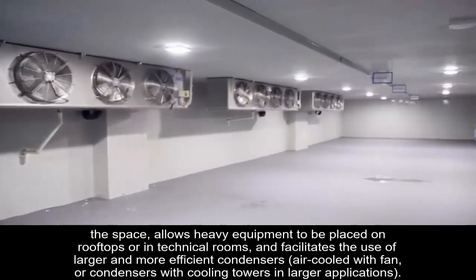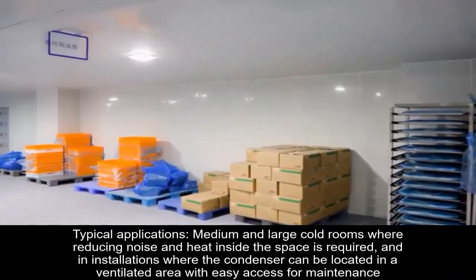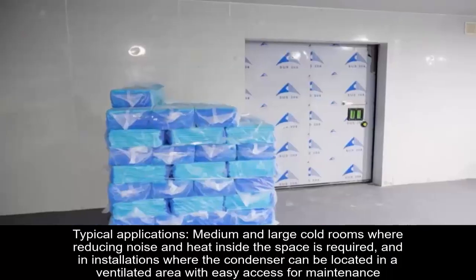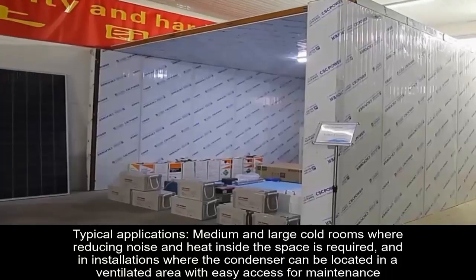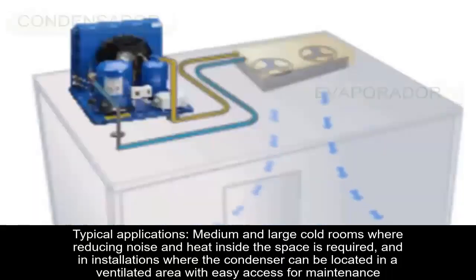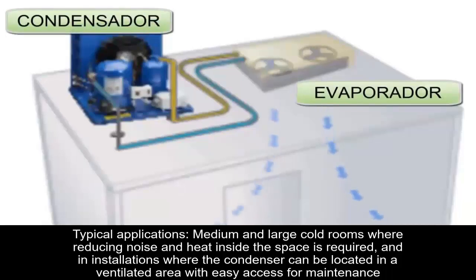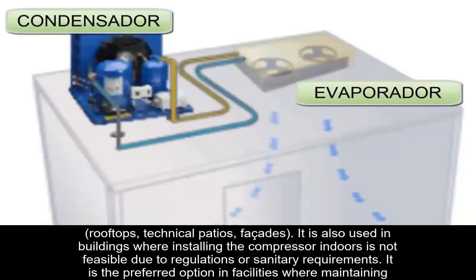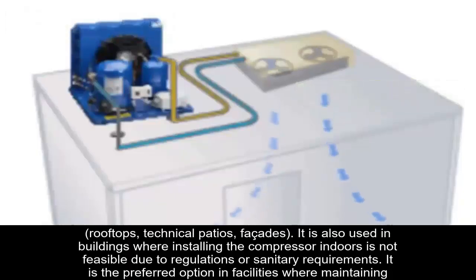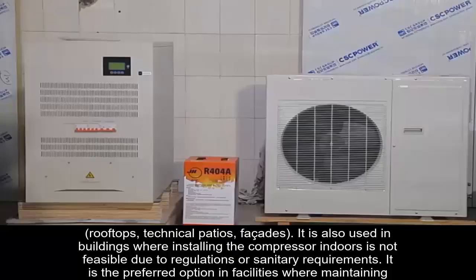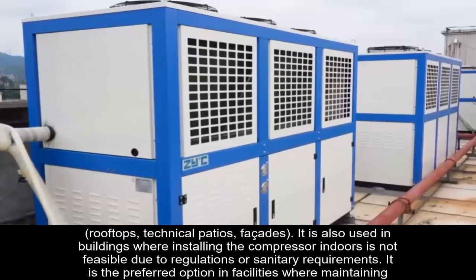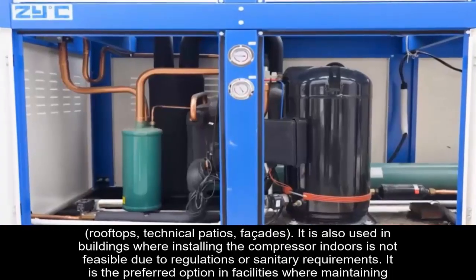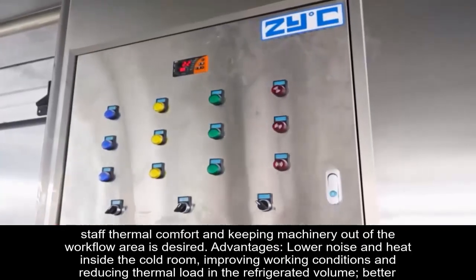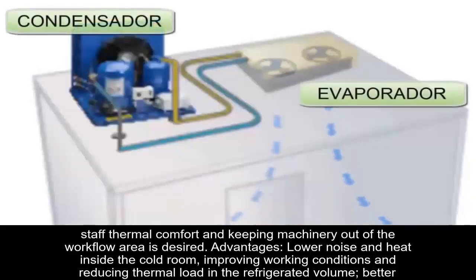Typical applications: medium and large cold rooms, where reducing noise and heat inside the space is required, and in installations where the condenser can be located in a ventilated area with easy access for maintenance: rooftops, technical patios, facades. It's also used in buildings where installing the compressor indoors is not feasible due to regulations or sanitary requirements. It's the preferred option in facilities where maintaining staff thermal comfort and keeping machinery out of the workflow area is desired. Advantages: lower noise and heat inside the cold room, improving working conditions and reducing thermal load in the refrigerated volume.